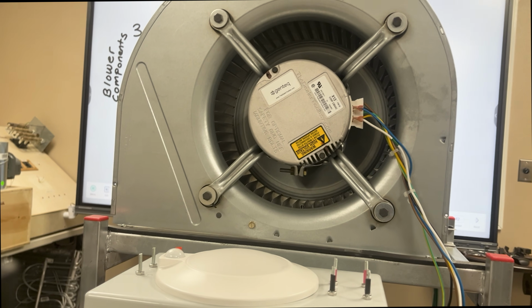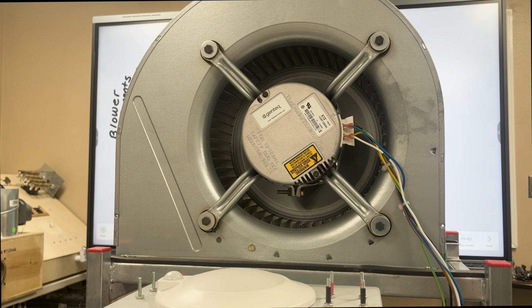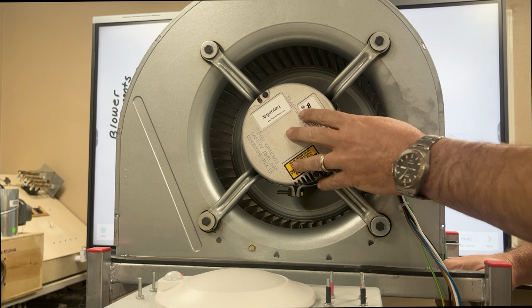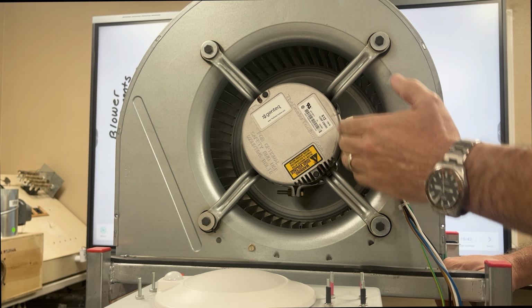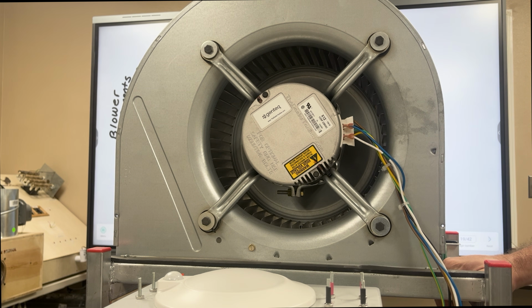We're going to discuss the 230 volts. And I'm also going to wire it to 120, which is not something that you're going to do in the field, but just to show you that this motor can run on 120 volts too. It's not running properly because this motor was wound to run for 230 volts of electricity, not 120 volts. But still, even PSC motors, you can create a path between common and run and still run it. You're going to obviously be outside of the amp draw that you're supposed to be, because if you drop your voltage, you raise your ampacity. So it's not something you would leave with a customer, but if you wanted to take this home and plug it into the wall, mess around with it, I want to show you that you can do that.